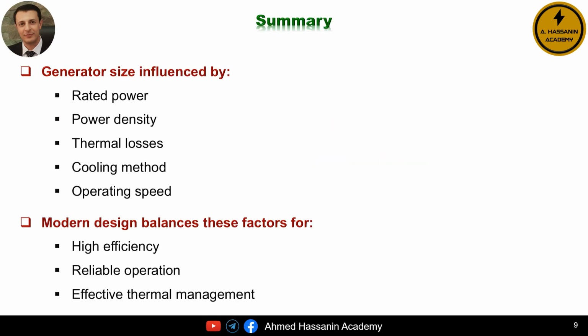All right, let's wrap everything up and connect the dots. The size of a synchronous generator is not chosen randomly. It's the result of several interacting factors. The rated power sets the basic scale of the machine, while power density determines how much output we can squeeze into that size. As power increases, thermal losses become more significant, and that immediately brings cooling requirements into the picture. On top of that, the operating speed of the generator strongly affects both its physical dimensions and how easily it can be cooled. In modern generator design, engineers are always trying to strike the right balance.